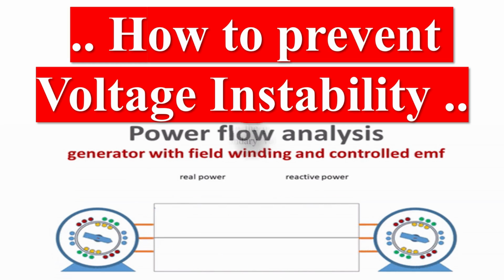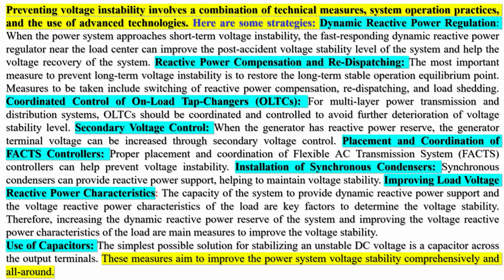operational risk. How to prevent voltage instability? Preventing voltage instability involves a combination of technical measures, system operation practices, and the use of advanced technologies. Here are some strategies. Dynamic reactive power regulation. When the power system approaches short-term voltage instability, the fast-responding dynamic reactive power regulator near the load center can improve the post-accident voltage stability level of the system and help the voltage recovery of the system. Reactive power compensation and redispatching. The most important measure to prevent long-term voltage instability is to restore the long-term stable operation equilibrium point. Measures to be taken include switching of reactive power compensation, redispatching, and load shedding. Coordinated control of on-load tap changers (OLTCs).